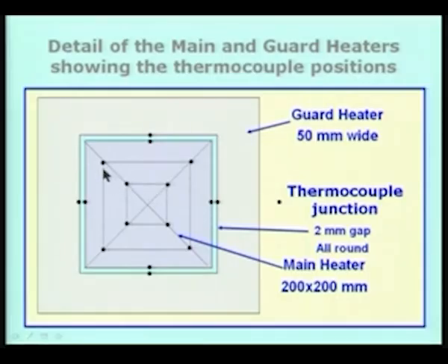And the other point is that we are going to measure the temperature not at a single point, but we are going to measure temperature as I have shown here. For example, 8 temperatures are measured on one of the surfaces, and of course, there is another surface on the other side, okay, and also there is another surface on the cooled side.